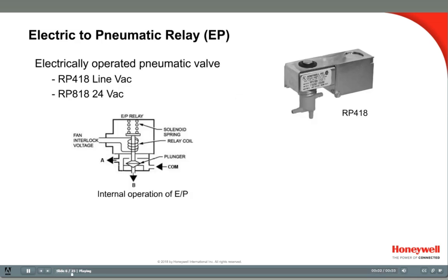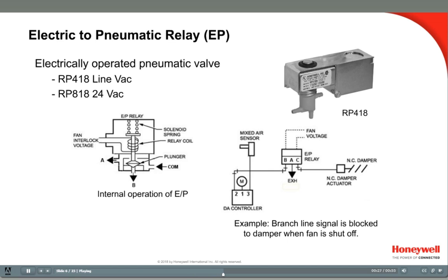A common relay is an electric-to-pneumatic relay, often referred to as an EP. It is an electrically operated solenoid connected to a 3-way air valve with a common port and a normally open and a normally closed port. When the solenoid is energized, the plunger moves the air valve to be open from the common port to the B port. When it is de-energized, a spring holds the valve open from the common port to the A port. The valve is often used as a pneumatic on-off valve controlled by either 24 volts or a line-volt electric signal.